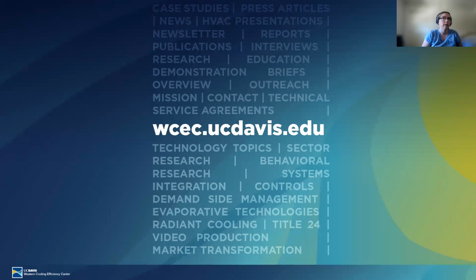Yeah, the reason I mentioned this 15 CFM is that the standards vary a little bit by state, but generally speaking, you're going to land at about 15 CFM per person for a classroom, and that's building code, right? That's a minimum building code requirement, and so that should be delivered anywhere, anytime, regardless of the weather. Building engineers design those HVAC systems to provide enough heating or cooling on the coldest days at that ventilation rate. So really there should be no problem. One of the issues is that because of the pandemic, people started opening up outdoor areas all the way. In that situation, you can't meet the building load, but you should be able to meet the minimum ventilation rate of 15 CFM per person.